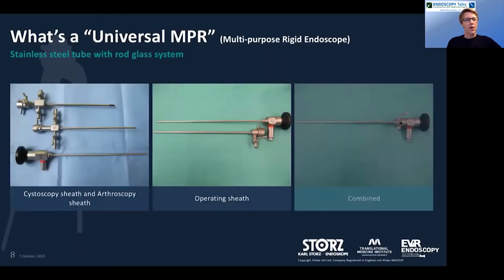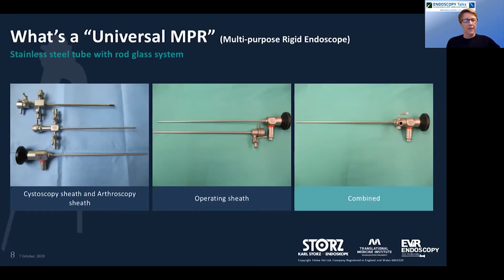So I want to start off with what's a universal MPR, or multi-purpose rigid endoscope. The multi-purpose rigid endoscope is a stainless steel tube, and it's got a series of glass rods inside the tube. And this is quite a fragile system. And the glass rods help illuminate and magnify an image. So compared to a disc system where you have a series of glass discs, the rod system tends to be quite a useful piece of equipment.